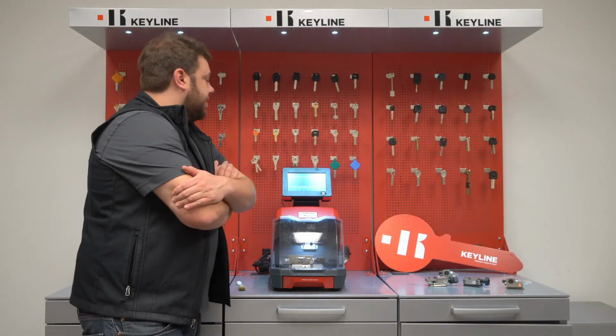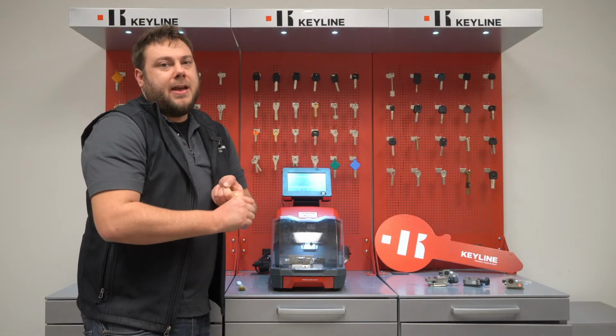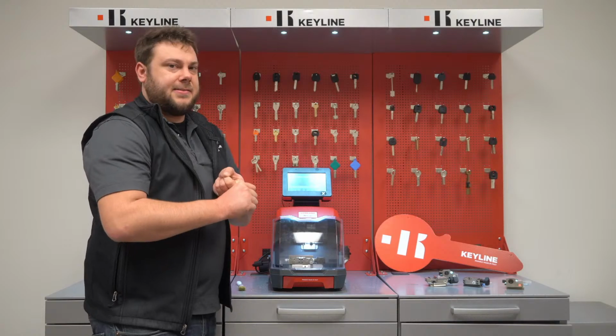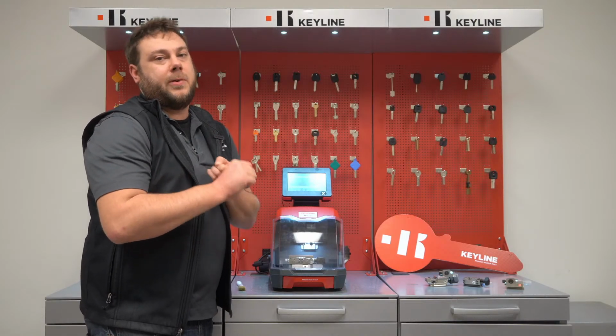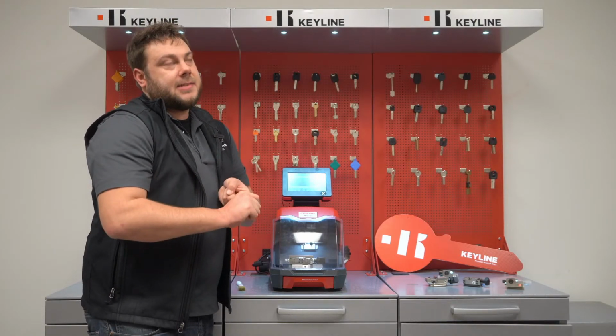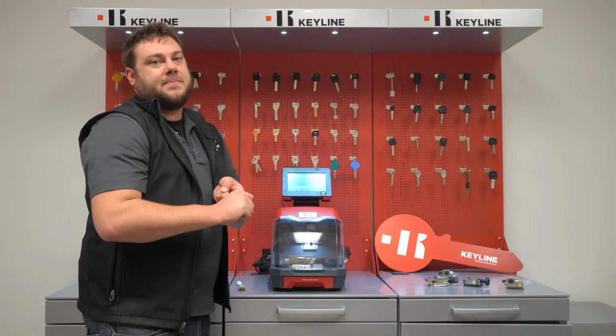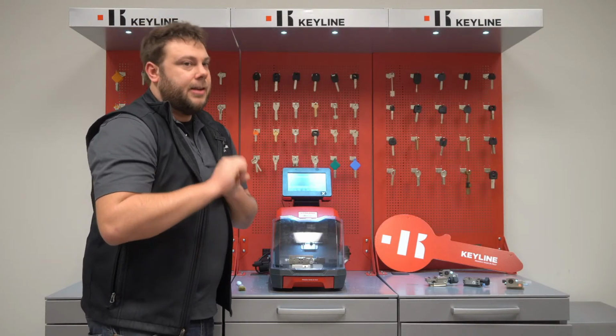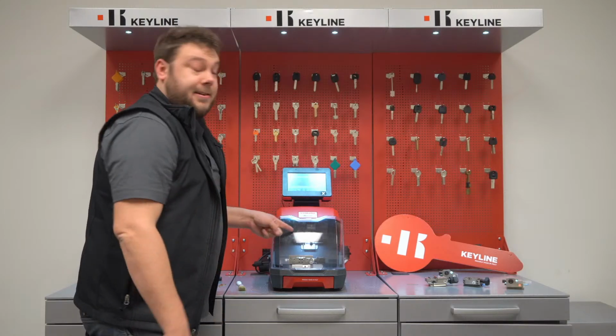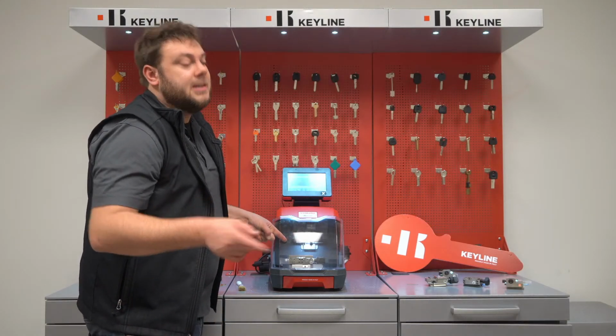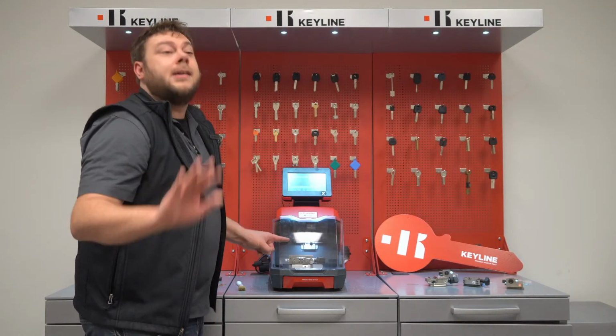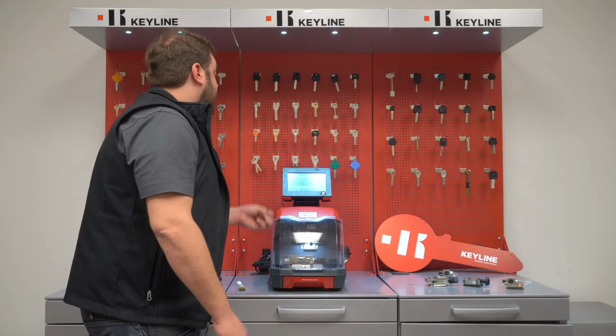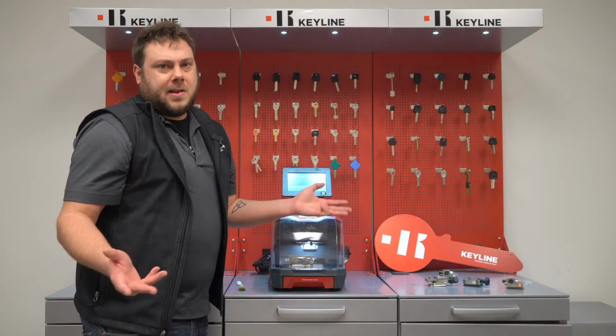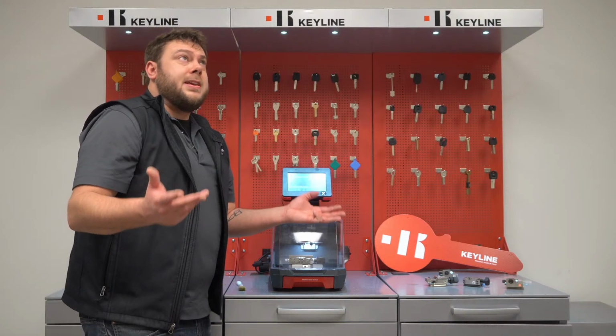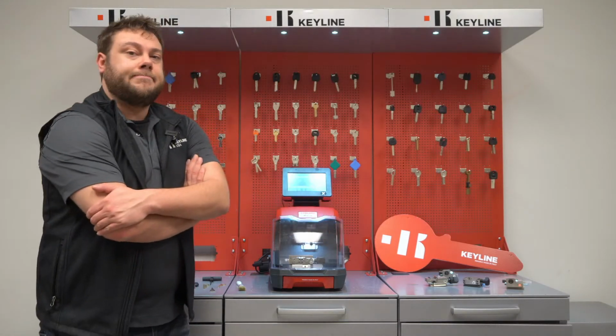But the big ones usually are invalid jaw. When you have the jaw installed, it means that the tracer's either touching or not touching the jaw where it's supposed to. "Please lift tracer" or "please lower tracer" error messages mean that the tracer knob is shifted. It'll shift over time, but that's why we have that sticker that says don't touch, so you shouldn't have to. But if it does, don't worry about it. A calibration should fix it. And reposition the key. Those are the top three user ones that I see all the time.